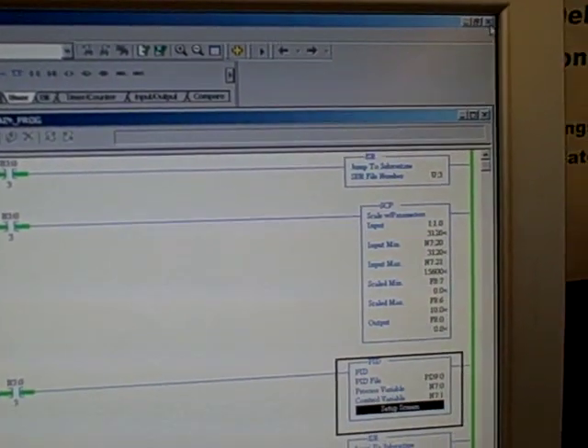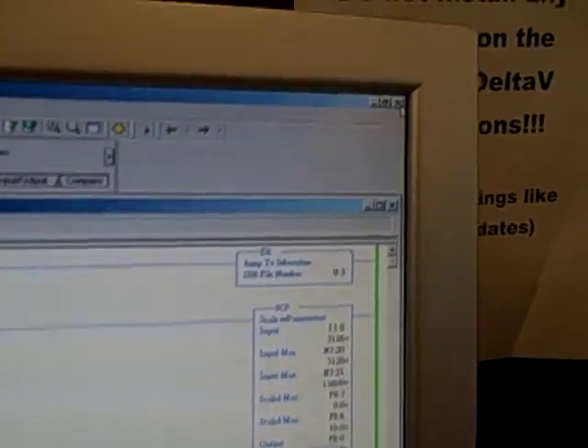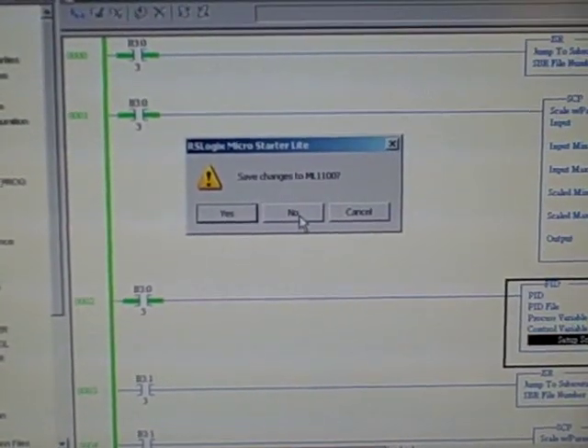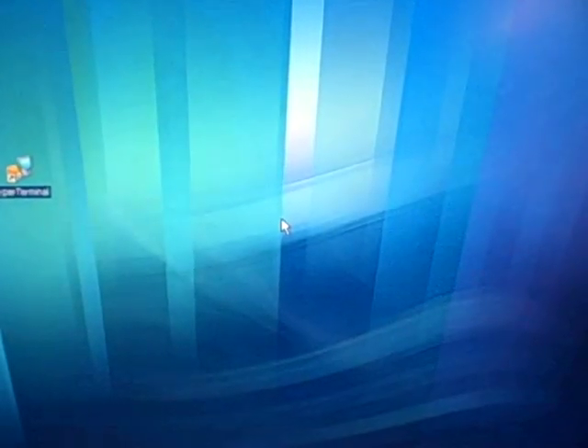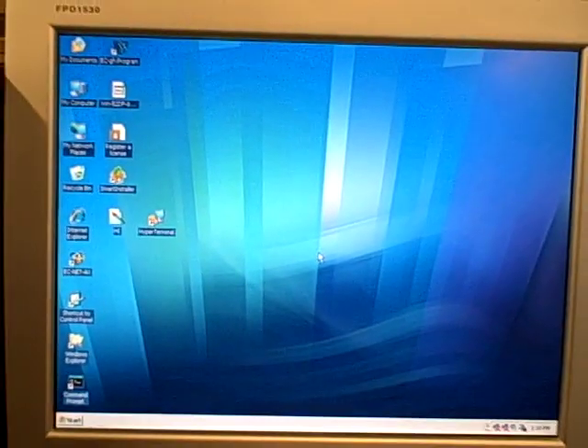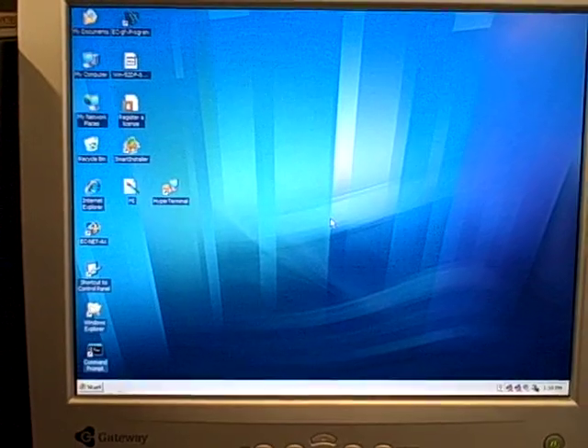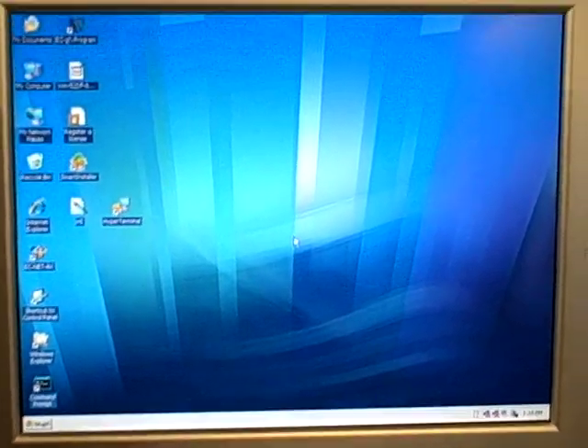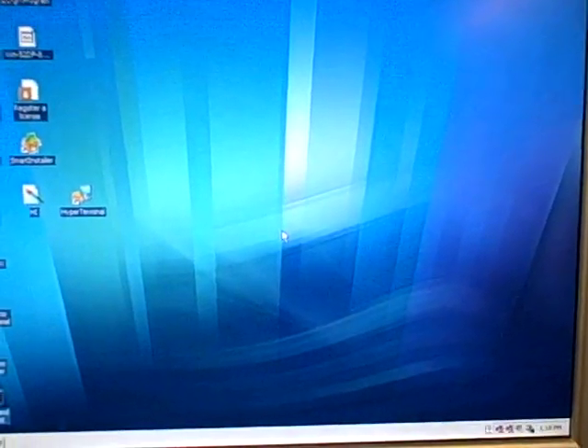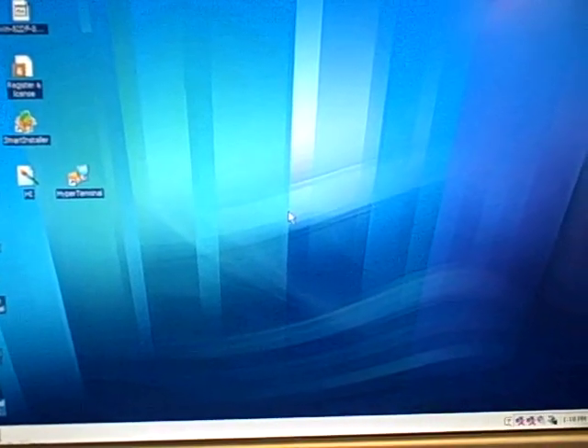At that point, you simply come up here, X out of the program, save changes. No, we do not want to save changes, because you've made the changes online. No need to save on the PC, no need to do a download. And that's about all there is to it, to configuring the basic parameters for one of these PID loops in the MicroLogix 1100 controller.